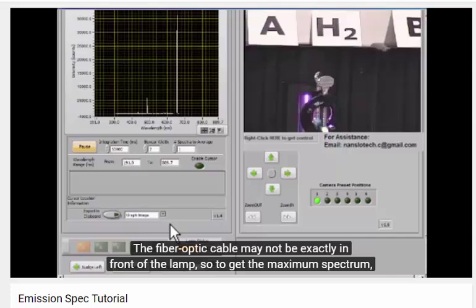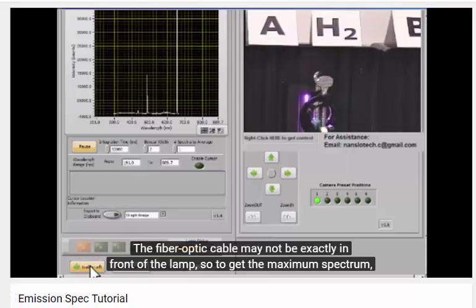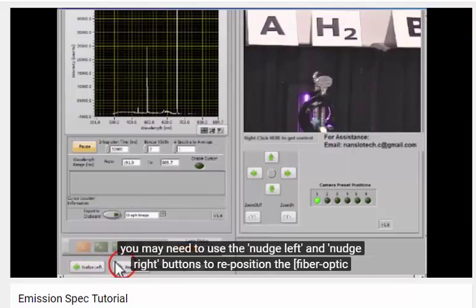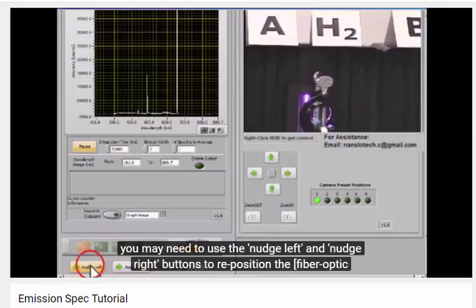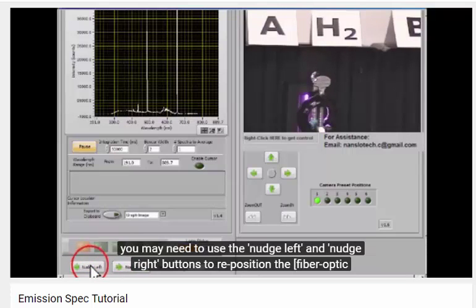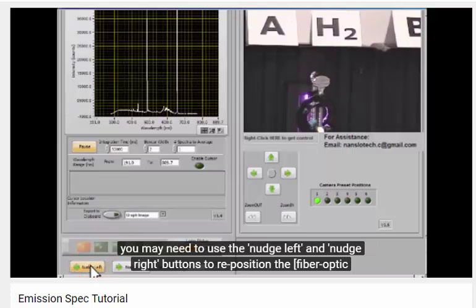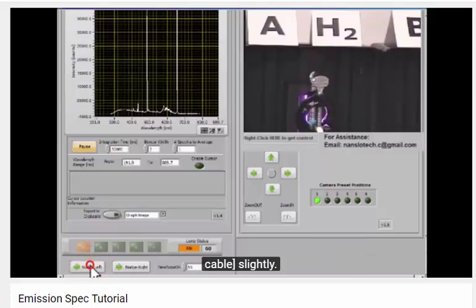The fiber optic cable may not be exactly in front of the lamp, so to get the maximum spectrum, you may need to use the nudge left and nudge right buttons to reposition the fiber-optic cable slightly. You can see that moving it left gives us a stronger signal.